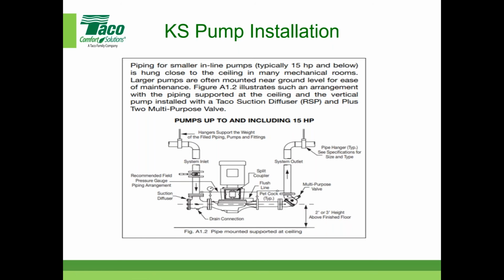Maybe you can tuck it and save some more space - think about your mechanical rooms. I've talked to many engineers over the years, and a common theme is mechanical rooms aren't getting any bigger, they seem to be getting smaller by the day. So here's some possibilities to save space on maybe a smaller type of system. Again, you have to think about maintenance, but if you put a KS pump up there near the ceiling, that motor doesn't have to be touched or moved, and that seal can be accessed - someone could climb a ladder or a scissor lift or whatever.